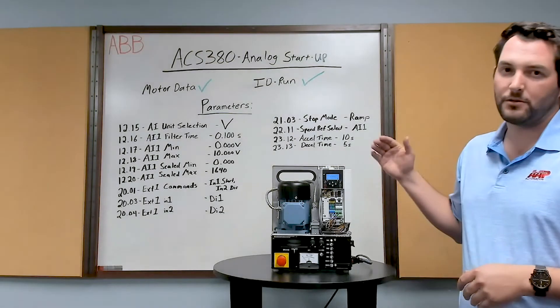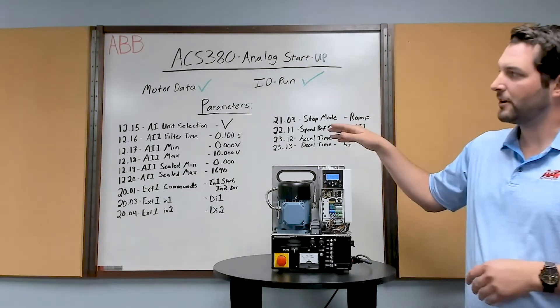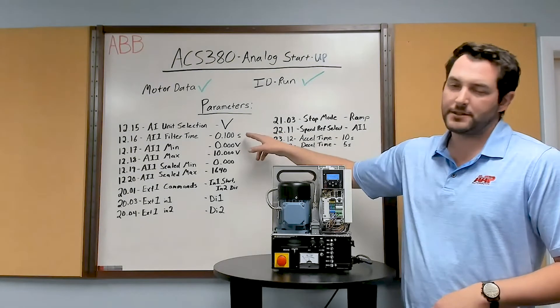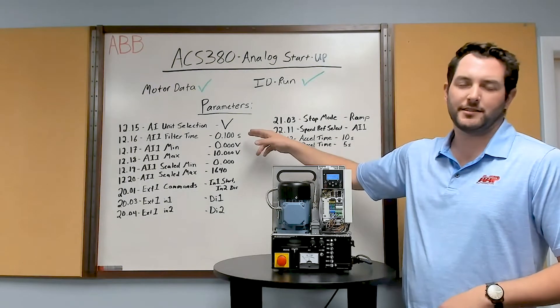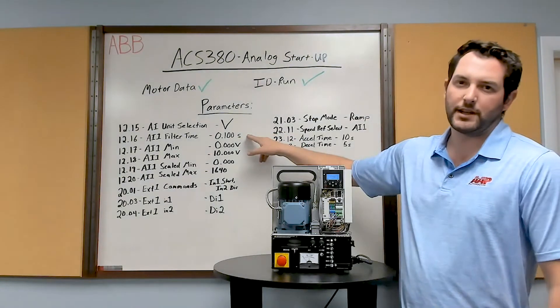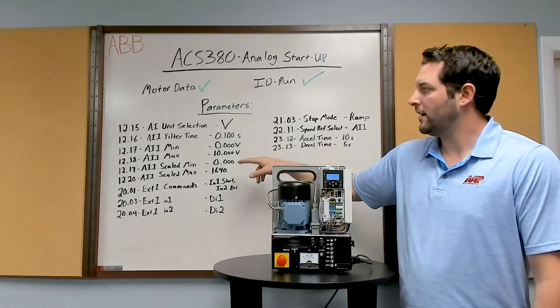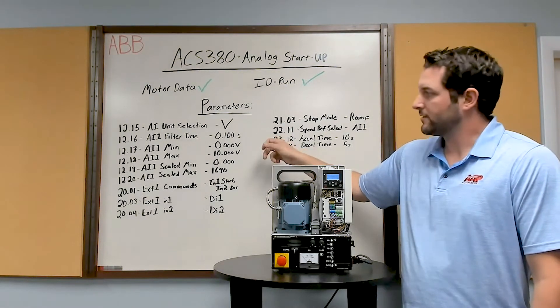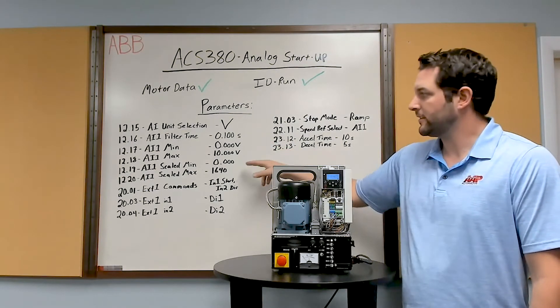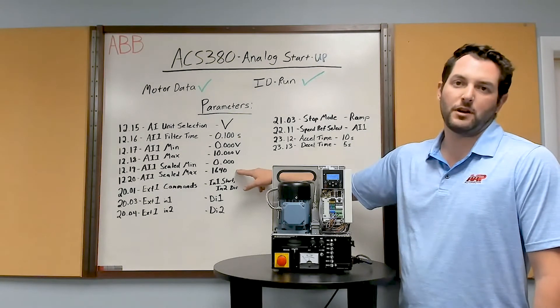To do that, we're going to go through about 15 parameters and we're going to start over in group 12 with our analog input selection — so it's volts and the filter time. The filter time is a time constant used to smooth out the signal and control the speed. It's defaulted to 0.1 seconds and we're going to keep it there; it's very rare that we ever change this. Our analog minimum is 0 volts, our maximum is going to be 10 volts, and we want to scale that to the speed of our motor — so 0 volts gives 0 RPM and 10 volts will give us 1640 RPM.